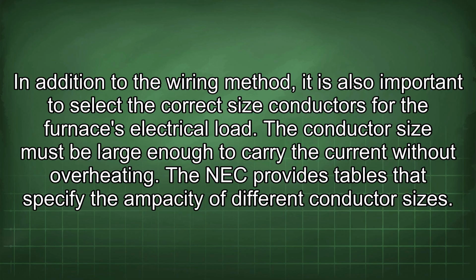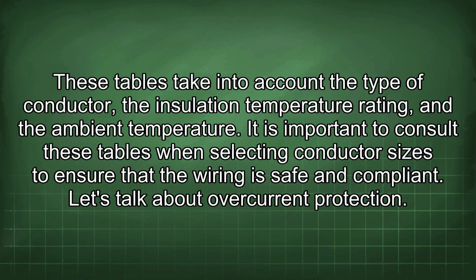In addition to the wiring method, it is also important to select the correct size conductors for the furnace's electrical load. The conductor size must be large enough to carry the current without overheating. The NEC provides tables that specify the ampacity of different conductor sizes. These tables take into account the type of conductor, the insulation temperature rating, and the ambient temperature. It is important to consult these tables when selecting conductor sizes to ensure that the wiring is safe and compliant.